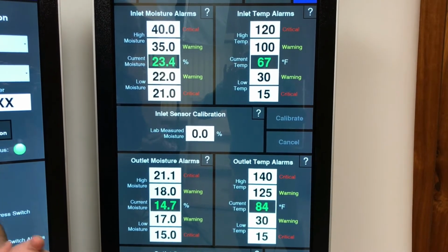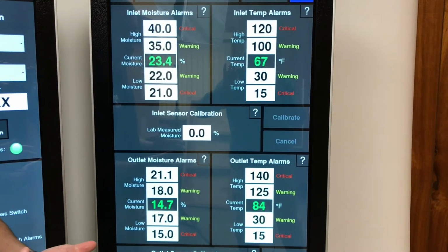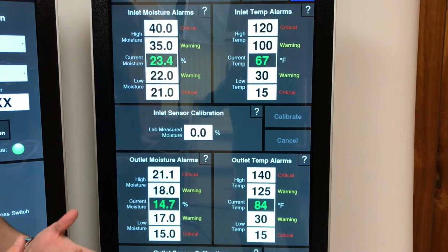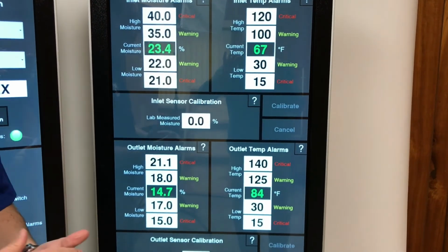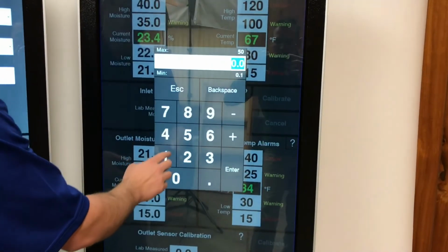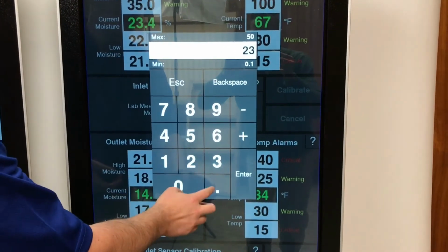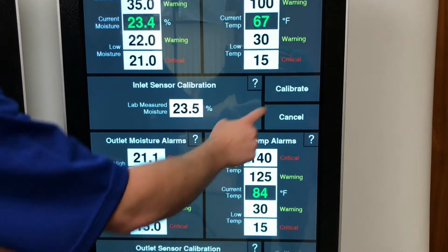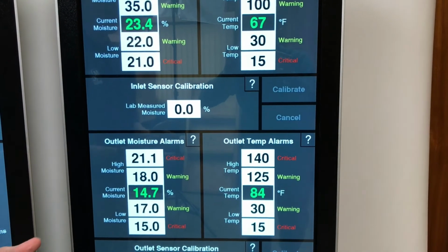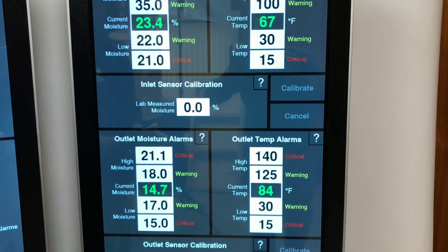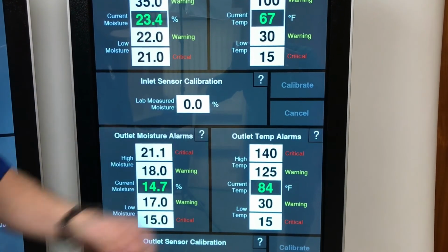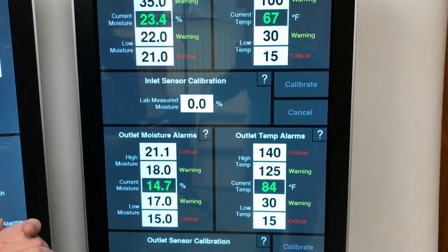So in this example, to calibrate a TrueDry sensor, it's a little bit more straightforward. What we'll do is you measure the grain, enter the value here, we'll put this at 23.5, and you hit calibrate. You don't have to start anything, you simply enter the value and hit calibrate. When it writes back to 0, you know that it's accepted your value.